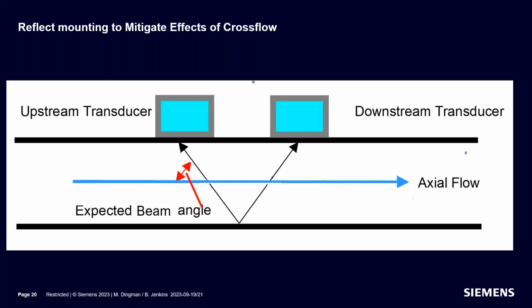And this is regardless of whether you're in direct mount or reflect. So if I was in direct mount, this transducer on the right would be down on the bottom, and I would just have one traverse across the pipe. But in reflect mount, you could see that the angle here and the angle on the right side would match. And this is no different than an airplane flying through the air. If it has wind on its nose, it's calculating its airspeed based upon the angle of the wind. And so you need to know that angle. If that angle is wrong, your flow measurement would be wrong, or your airspeed indicator would be wrong.